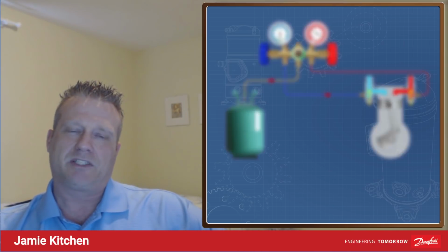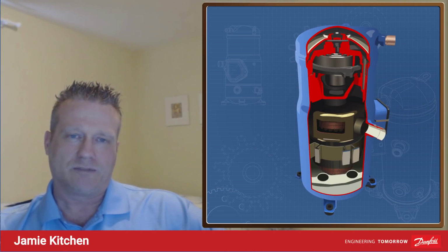So if you end up having a situation where you've got liquid return, poor superheat or poor metering control, you've got off-cycle migration, right? That upper bearing is going to fail. I don't care what kind of compressor it is. In fact, scrolls in many ways are more prone to failure because of that than other types of compressors. So don't be fooled into thinking that a scroll compressor is this bulletproof thing. All right, trust me, I know.